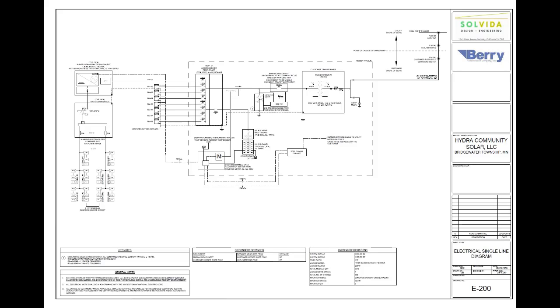Certainly. Similar in nature, different developer, different engineering group, but as we said, this is mid 2019 in this site here, but very similar layout to some of the drawings and designs we've just reviewed. We have strings of inverters to an AC combiner board. In this case, though, what is perhaps a little more difficult to see is the board was essentially a blank slate, and the customer metering, the station power, the different disconnects were grouped outside of the switchboard. I should say the main disconnect still resided within the AC switchboard, but most metering was located outside of it.